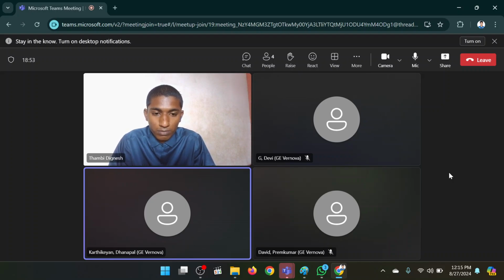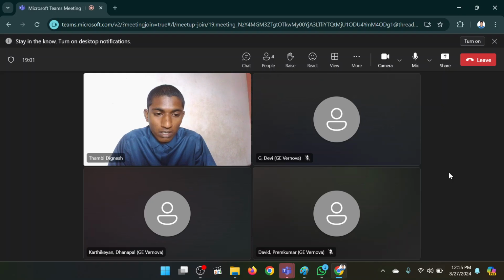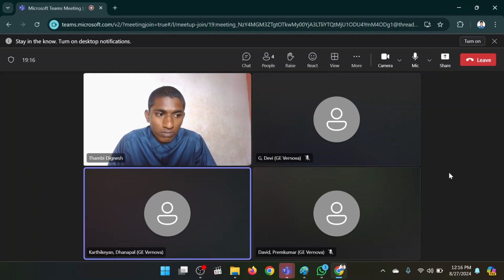That is not the circuit, sir, because we are having one more circuit supervision in the panel. So you know about that? Sir, I think that is for AC supervision and DC supervision. No, no. AC supervision and DC supervision is for supply supervision. This is trip circuit supervision. Next, coil supervision is coming from the breaker. Trip circuit supervision is to monitor the supply in the 86 relay. Suppose in case of the 86 tripping relay, anything has happened or the coil is getting open, then by means of trip circuit supervision it will monitor that circuit. Okay, sir.